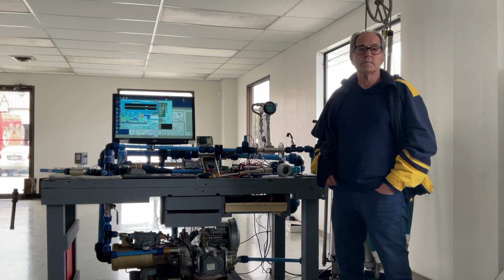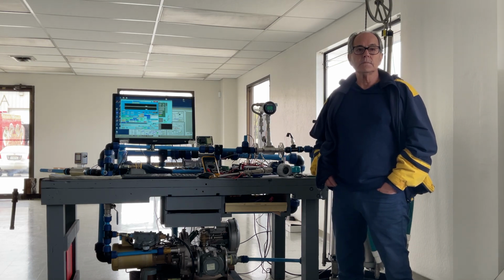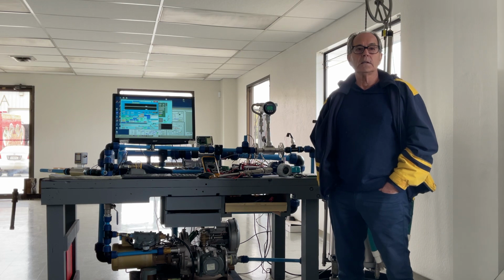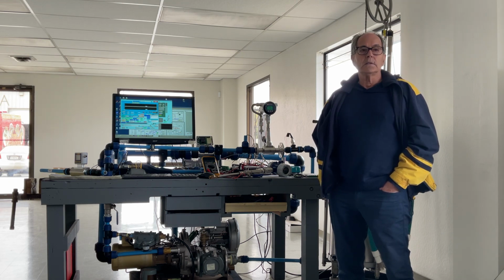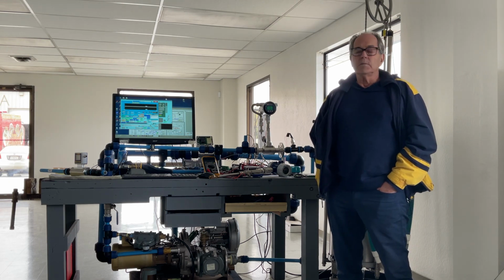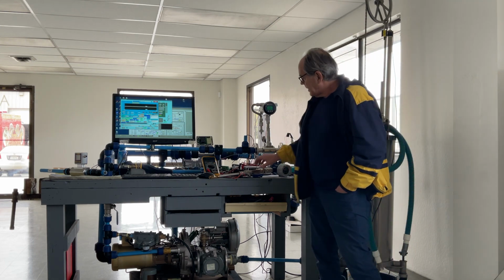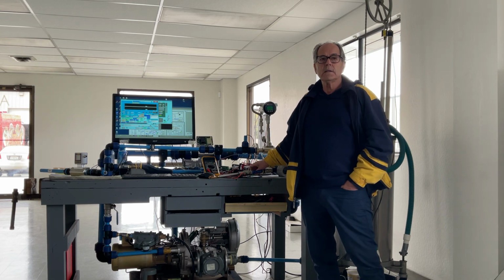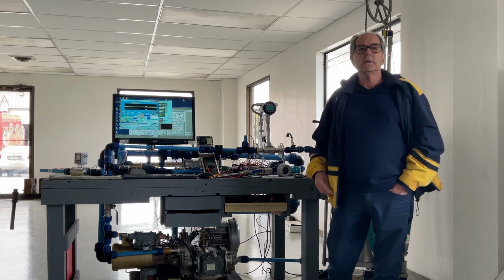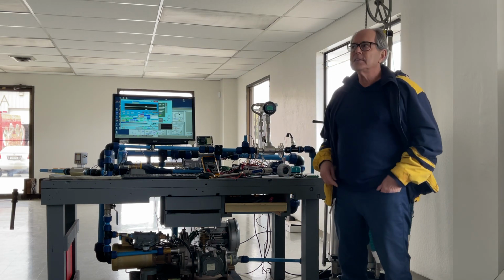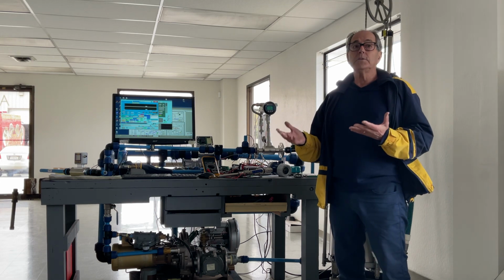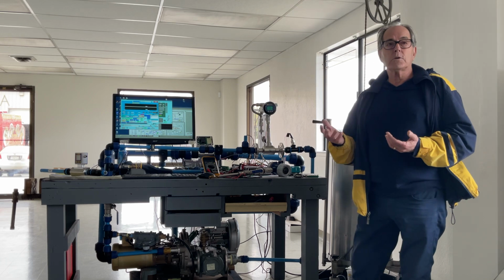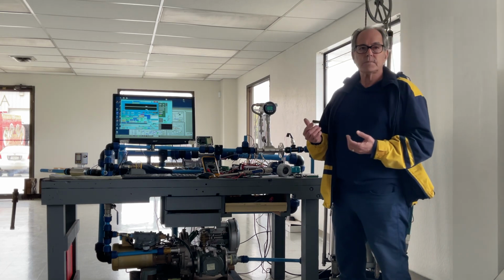And just one question, when you say time domain, I remember that anything that has an output that's frequency is in the time domain, is that right? Yes. And if something has an output that's in volts, that's the amplitude domain? I don't know what domain it's called. It doesn't matter. By time domain, all we mean is that we have an output that's a frequency, and we're mapping a frequency to a flow rate. Time domain is pretty nice because it's simple to trace it back to something, because crystal oscillators are cheap.